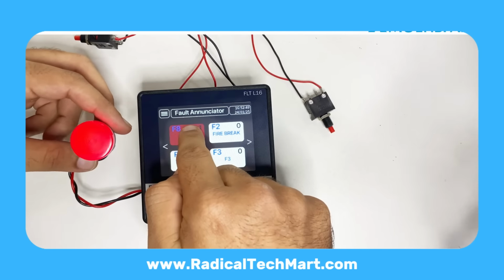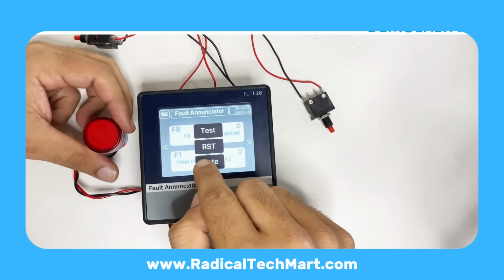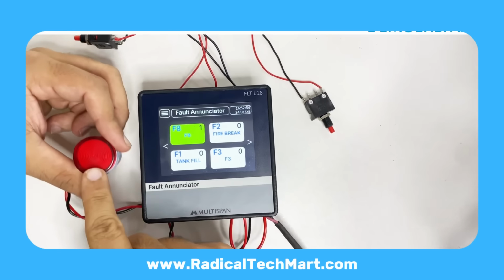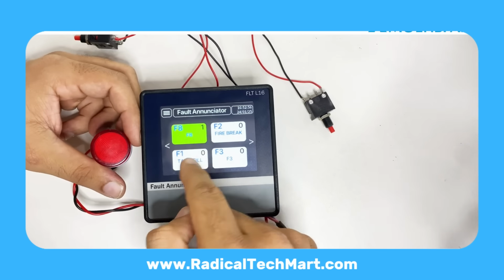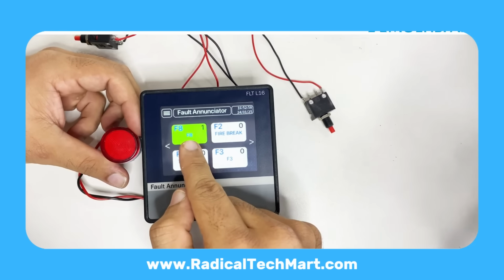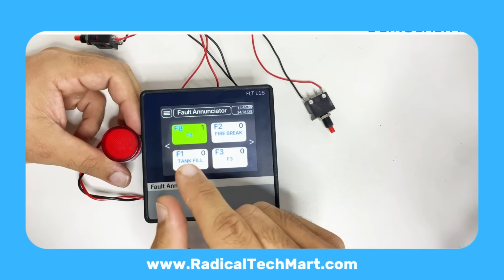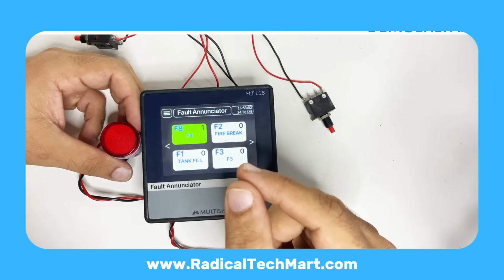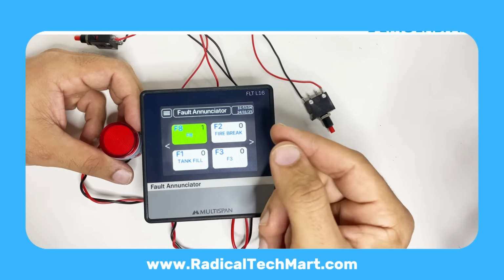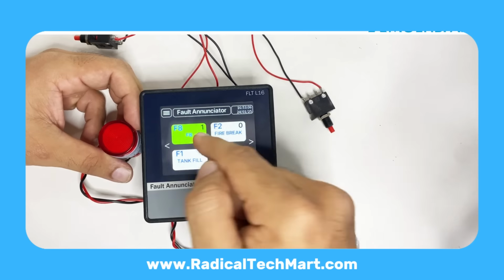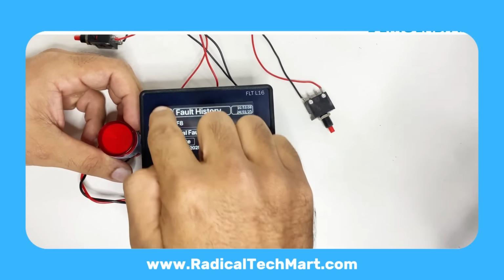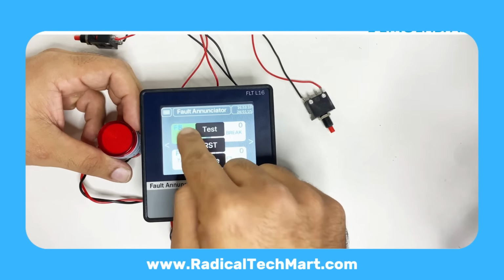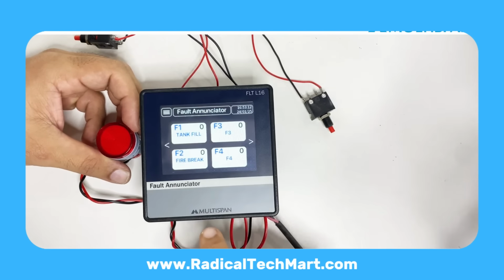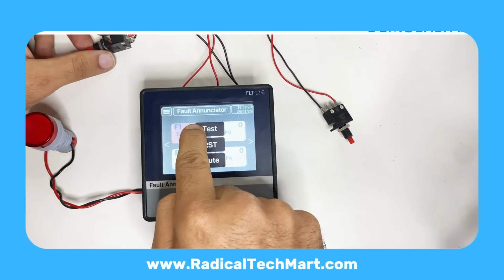To mute the alarm, press and hold the mute button. Once muted, the fault window color changes to green. Green means fault occurred, but acknowledged. Field status is now healthy or acknowledged. To fully reset the fault, press and hold reset and confirm. After the reset, all the fault windows turn white, indicating no active fault in the system.